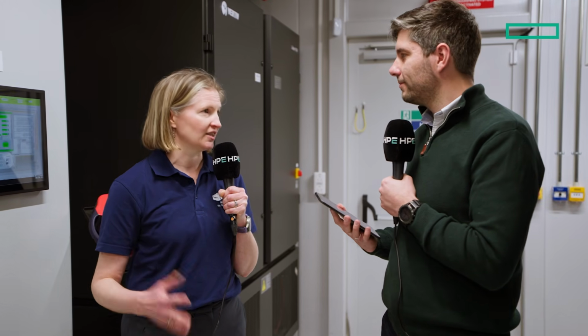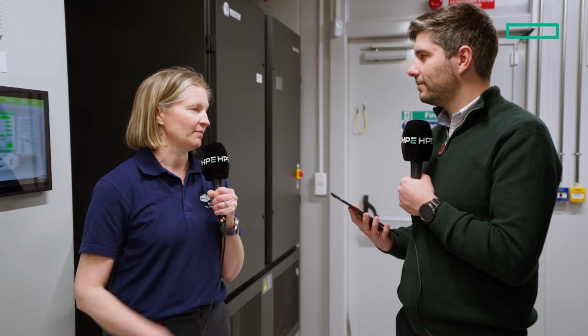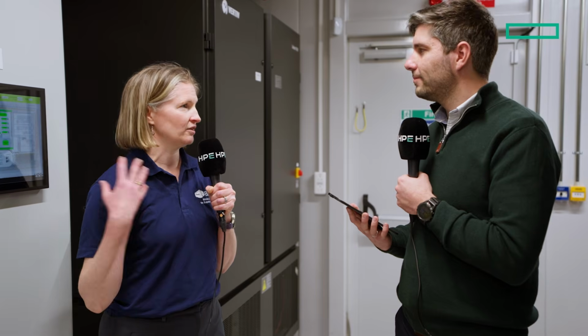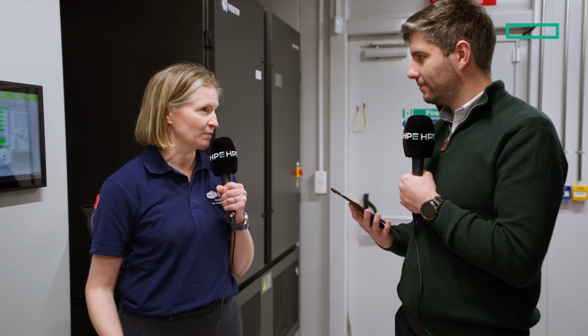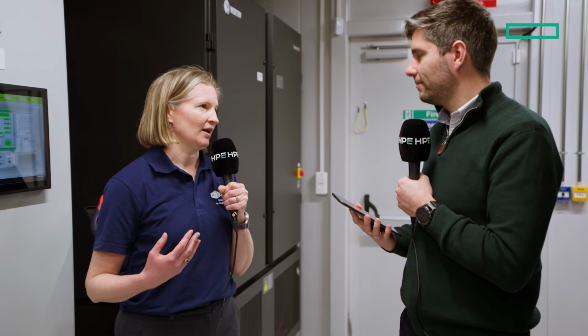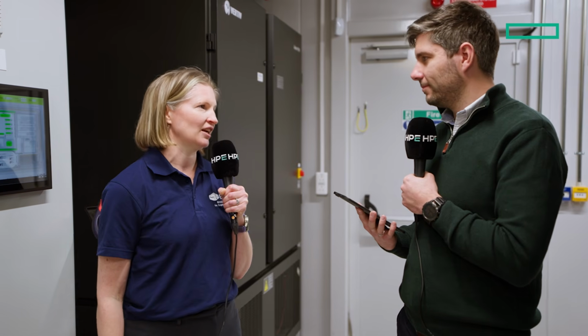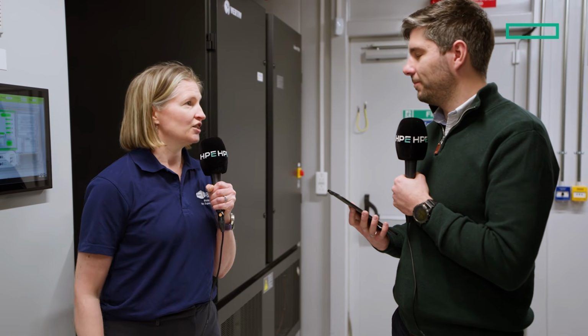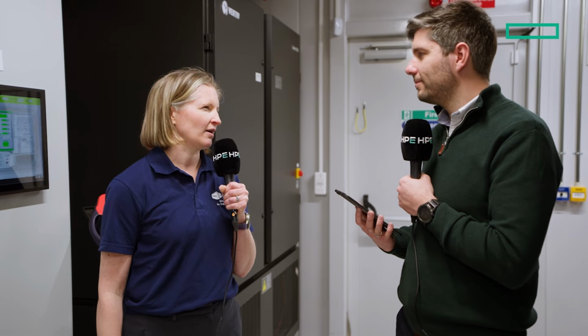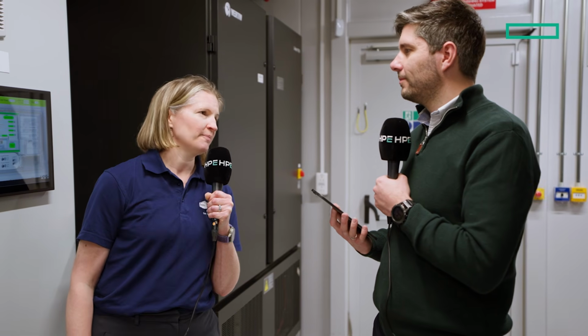The cooling, for instance, we would want to keep going in the event of a power cut. We've also got some air-cooled equipment that runs our storage and our login and management nodes. We need that to keep going, because if it shuts down suddenly, it takes a long time to bring back up again. So we have a generator on site that will keep it going for a few hours in the event of a power cut.